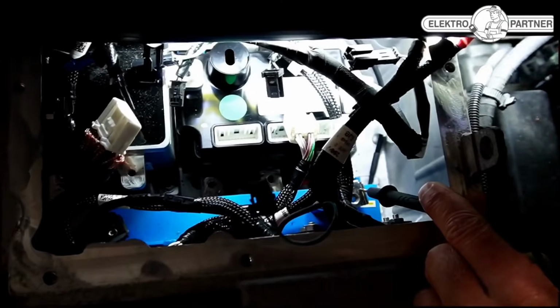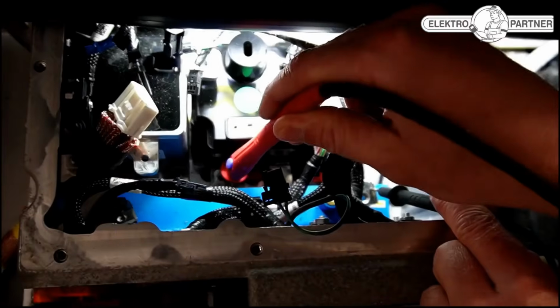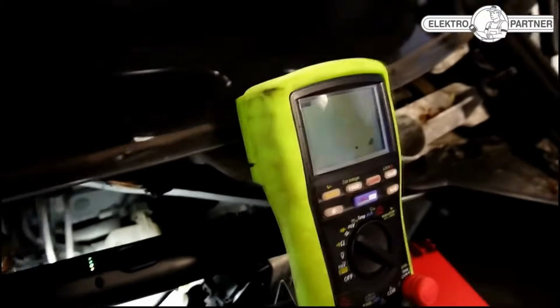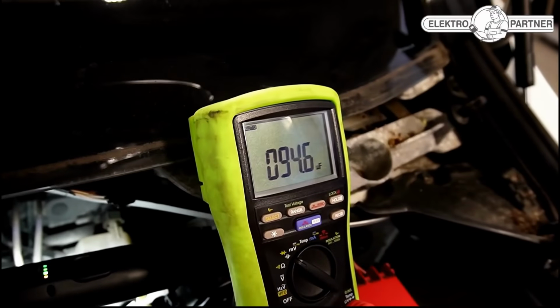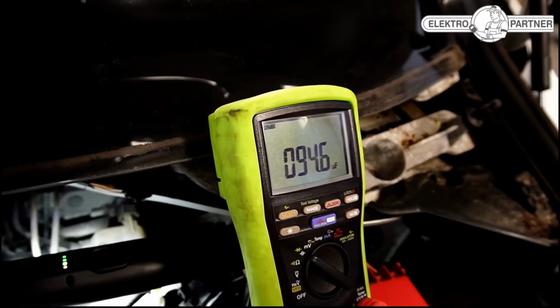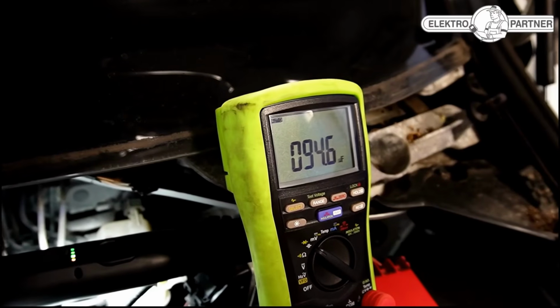So here we're testing ground, and then we measure the 3 phases, and we'll see if they're within 100 megohm. 94.6 — that's actually a decent measurement, because it can actually go all the way down to 90.